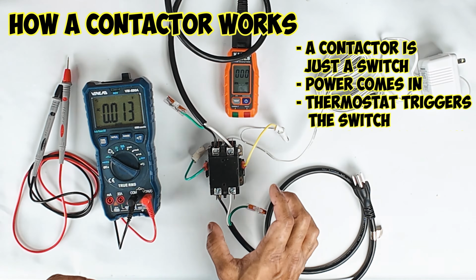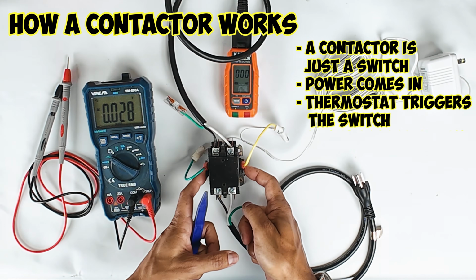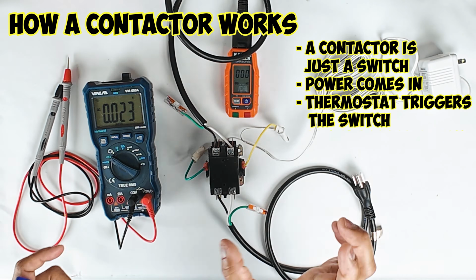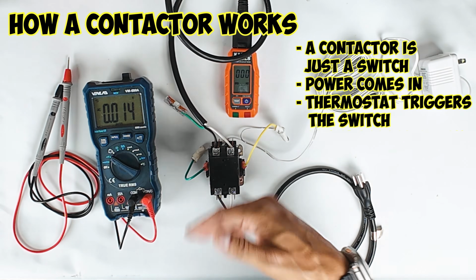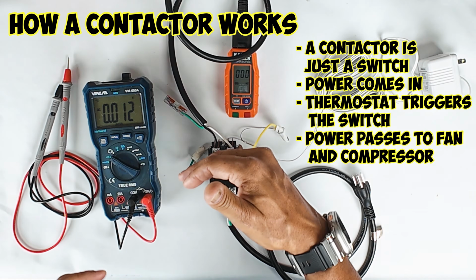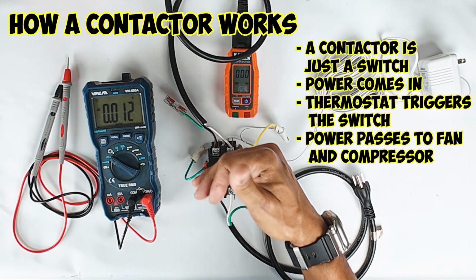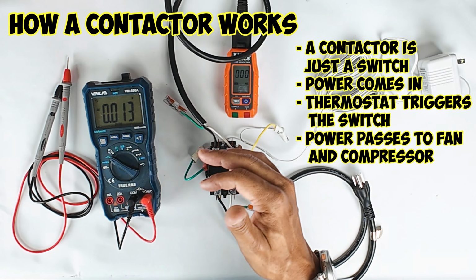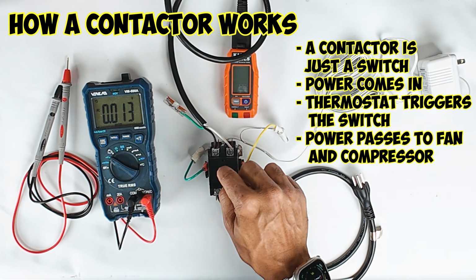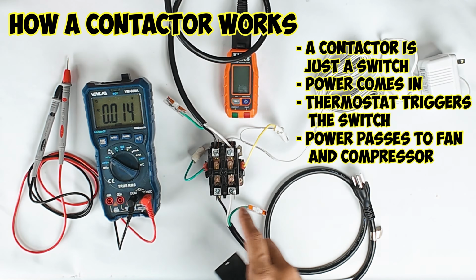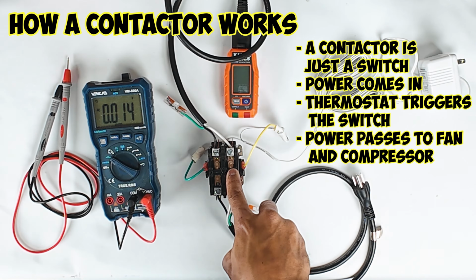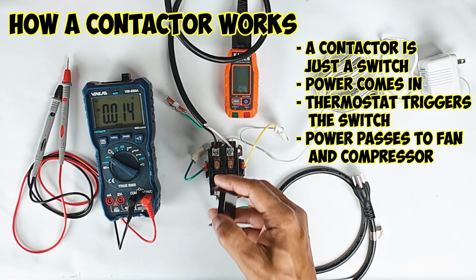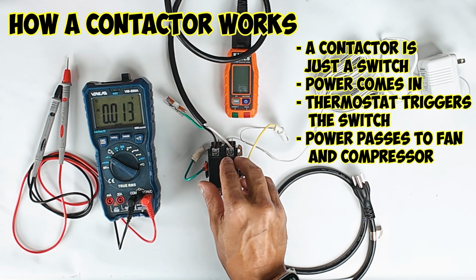It has an electromagnetic coil that's located inside here that gets 24 volts. It closes the contactor and the voltage passes through the contactor to your compressor and your fan to start the cooling or heating process. Most contactors have a manual button, but this one is covered, as you can see here. There's a button inside here, just like this, that you can use to switch this thing on and off if you need to test it.